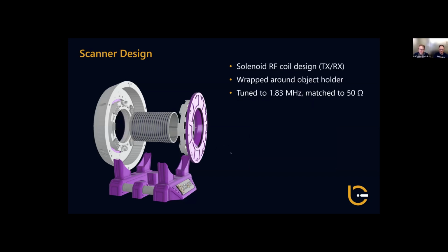And then the last component is the transmit and receive coil, the RF coil, which is indicated in blue here. This is basically a solenoid coil with, I think, 20 windings. It's wound around the object holder here, has been tuned to a frequency of 1.83 megahertz and matched to 50 ohms. And the inner part here is the object holder where you can place an object inside. If you look into the scanner from the outside, basically this is what you would see, the object holder here. And this is basically the basic design of the scanner.